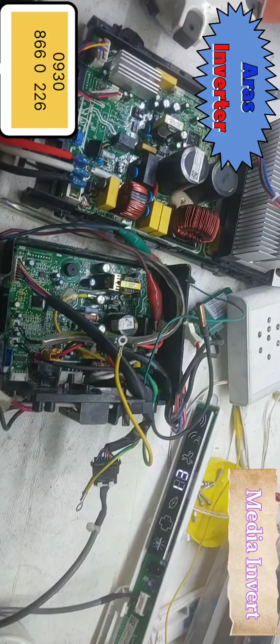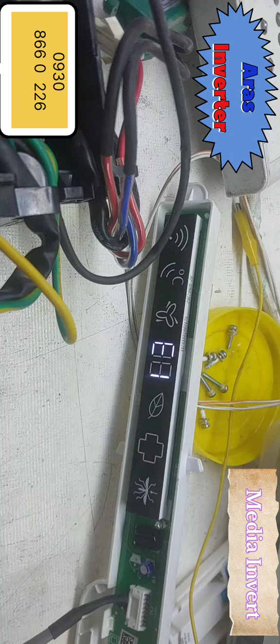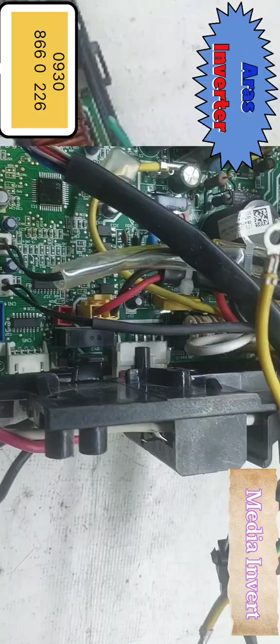Error code E1: communications error between indoor and outdoor units. This error often occurs as a secondary effect if the outdoor fan fails to start. The outdoor unit's compressor and electronics can quickly overheat.